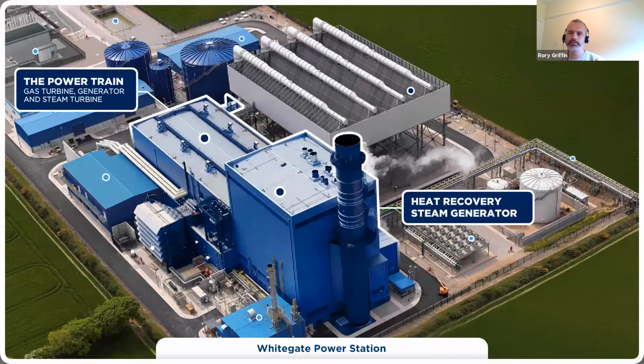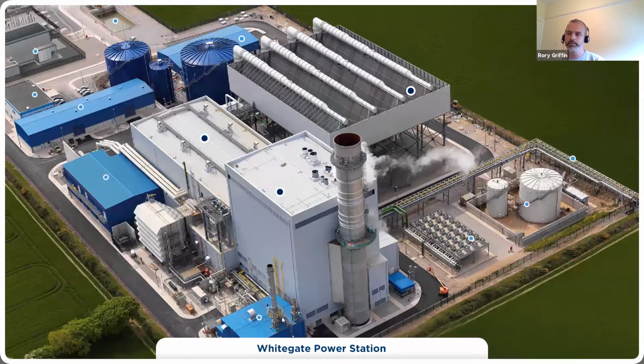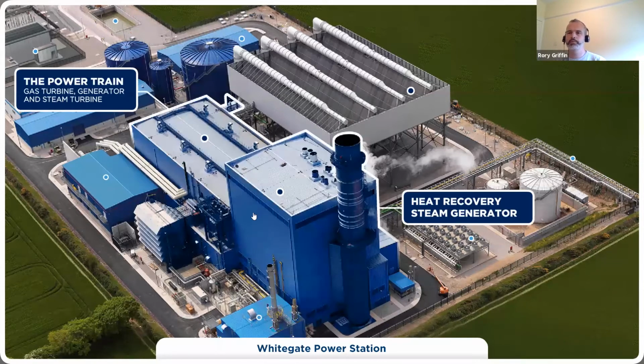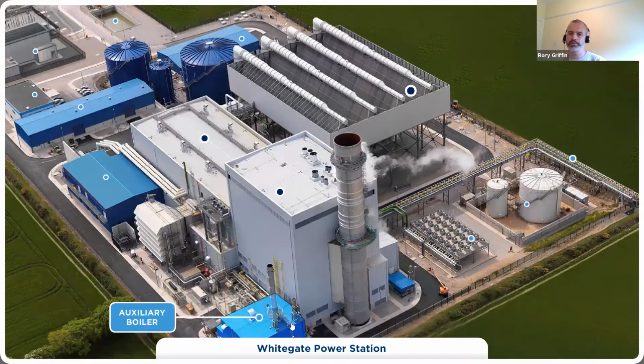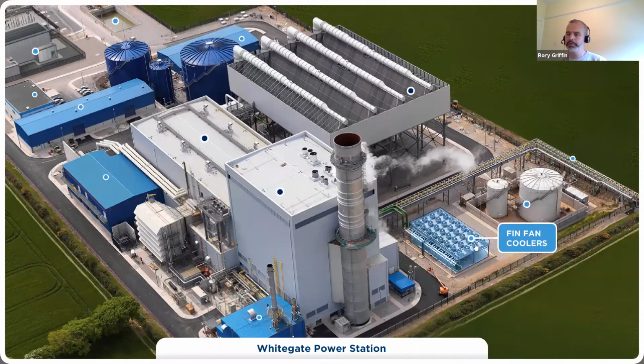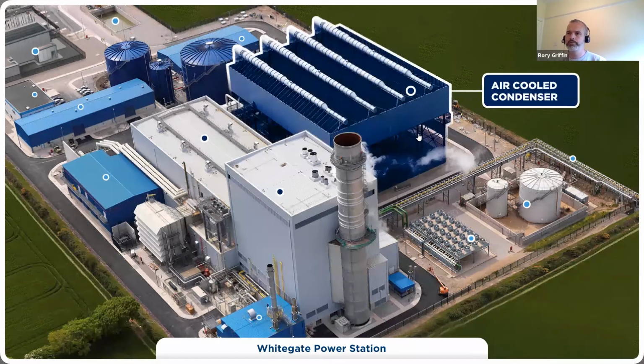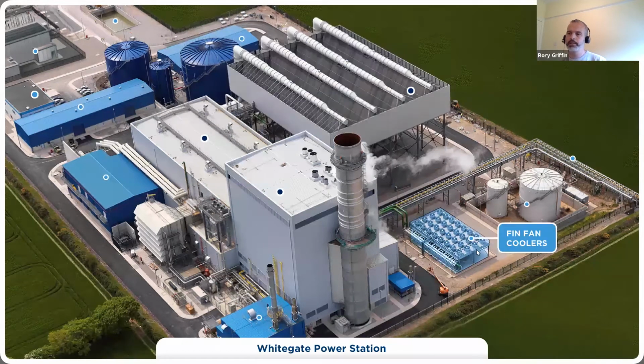This is the filter house for the air intake to the compressor. We'll discuss that shortly. And down here in the bottom of the screen is the auxiliary boiler. The auxiliary boiler is key to the plant starting up. If Whitegate is in an offline state and it gets an instruction from the grid to come on, the first thing that happens is the auxiliary boiler is started up. It produces steam, which is then used to pull vacuum and also to provide seals on the steam turbine. If the auxiliary boiler doesn't start, Whitegate isn't coming on, basically. Along the bottom here, we have fin fan coolers. This is a mini version of the air-cooled condenser, which I'll discuss shortly.